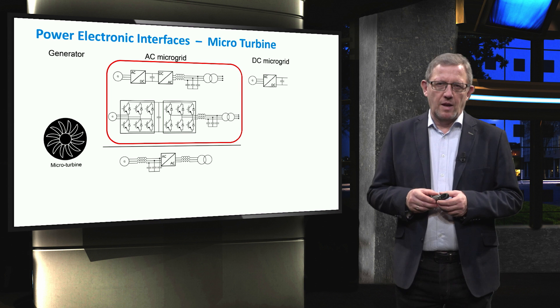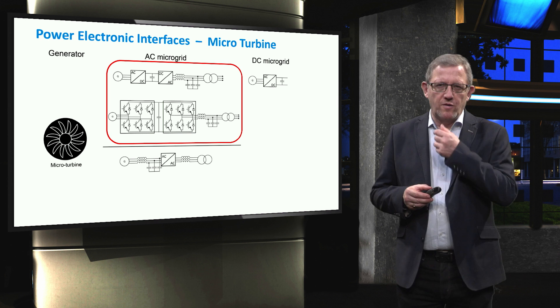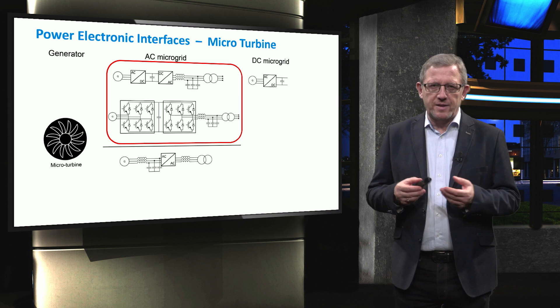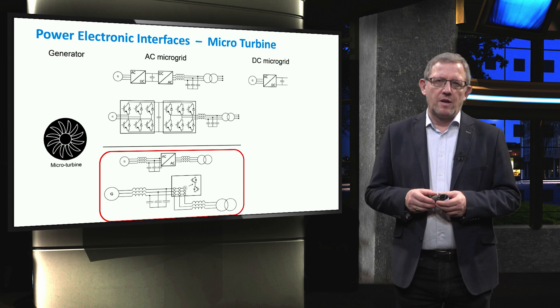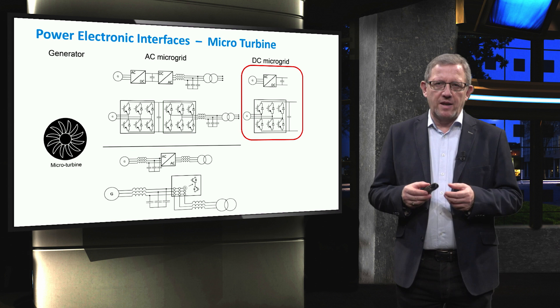The last component for today will be the microturbine. Similar to wind turbines, they can be connected to an AC microgrid through a full back-to-back converter. They can also be connected using new types of power converters like the matrix power converter, which is a direct single-stage bidirectional topology. Due to its large flexibility and controllability, this converter has become a very popular topology. Similarly to wind generators, a microturbine can be connected to a DC microgrid in the simplest form by a three-phase AC to DC rectifier.